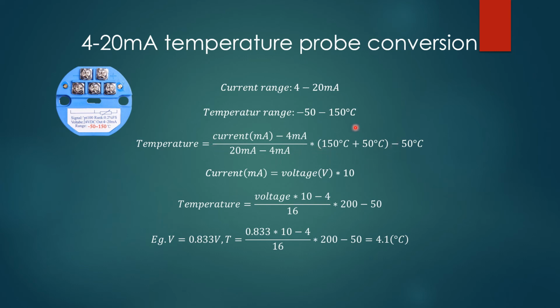And then we multiply by the target temperature range. The temperature range is 150 minus negative 50, or 150 plus 50. And then we must also add the starting point, because this only gives you where you are within your range of 200 degrees, but your starting point is minus 50 degrees C. That gives you the resulting temperature. Again, if you're using my 4 to 20 milliamp extension board, the voltage you read multiplied by 10 is the current. Then that current minus 4 divided by 16 converts it into a fraction of the current range, and then multiply by 200, then minus 50.